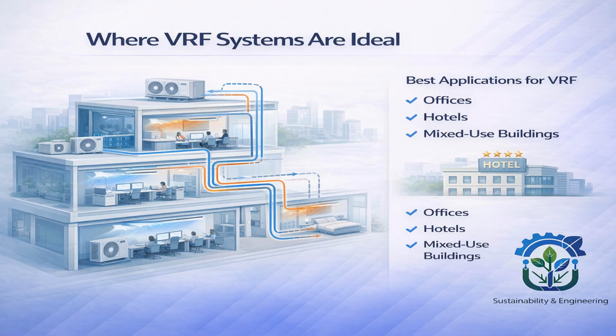Next, let's look at mixed-use buildings. Mixed-use buildings combine offices, retail, residential or hotel spaces. Each of these spaces has different operating hours, different cooling profiles, and different comfort expectations. VRF systems handle this complexity very well because of their zoning and control flexibility. However, there is an important point to remember. VRF is ideal for medium to large buildings, multiple zones, and variable loads. But VRF is not automatically the best solution for every large building. Once cooling load becomes very large, or operation becomes 24/7, or fresh air and latent control dominate, we must start evaluating chilled water systems instead.